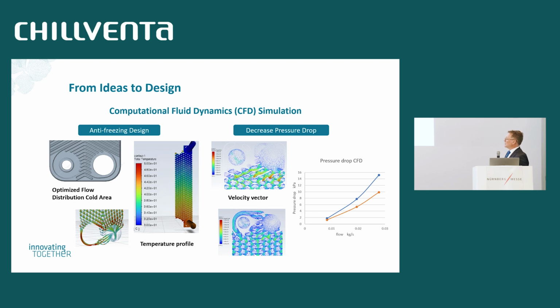You also use the CFD to decrease the pressure drop. With the tool, you can see what kind of velocity you have over the plate. You can then calculate the pressure drops over the plate, especially on the water side of the heat exchanger, where you would like to have as low a pressure drop as possible, to be able to use less energy for the pump in the system, and thereby create a better COP of the heat pump.